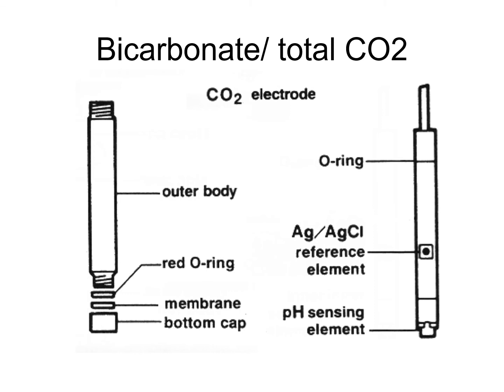So we can see here an example of that electrode that can detect carbon dioxide. It's made up of the same reference electrode, and there is a specific electrode for pH. And so that is the bicarbonate carbon dioxide electrode.